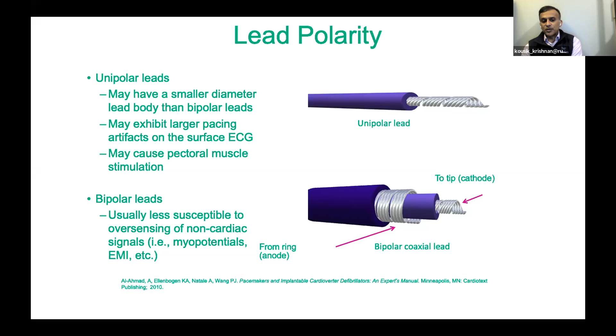The bipolar leads are a little more immune to oversensing from non-cardiac signals such as myopotentials or electromagnetic interference. So let's talk about a unipolar pacing system. A unipolar pacing system is a little bit of a misnomer in the sense that the lead only has one electrode, a cathode, but there is a second pole, and that anode is the device itself. So the bipole of the cathode to anode is very large.